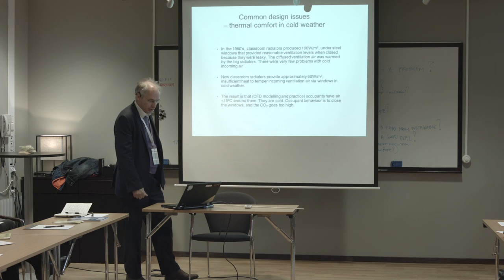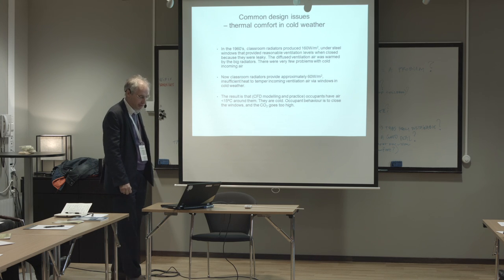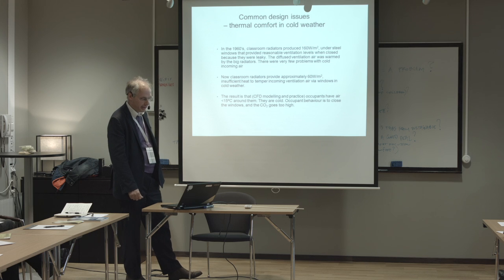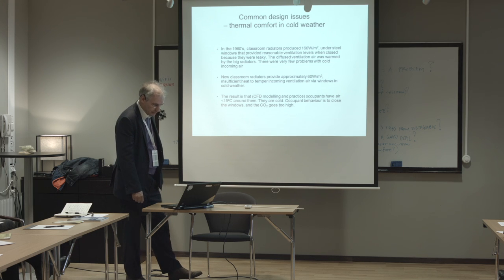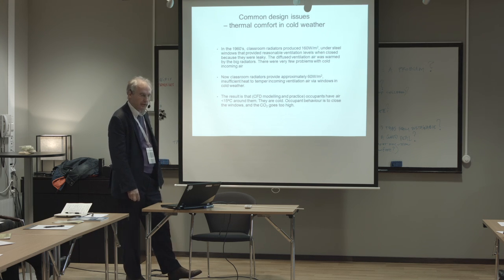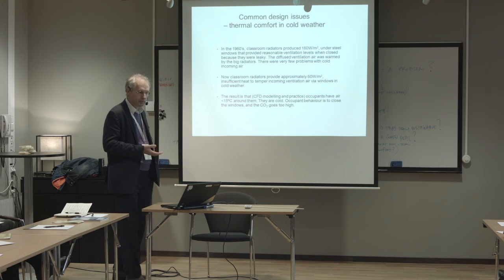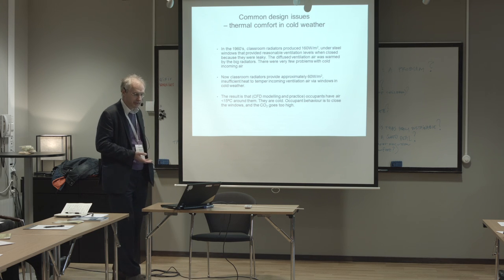We've got a very small classroom radiator — 60 watts per square meter, which is a maximum and could be a lot less than that. That's insufficient heat to temper the incoming ventilation air. So we've got to find a way to get the air, when it reaches the occupied zone, comfortable enough. We've introduced a new guideline which says that the supply air must be at least 15 degrees when it hits the occupied zone in the classroom.